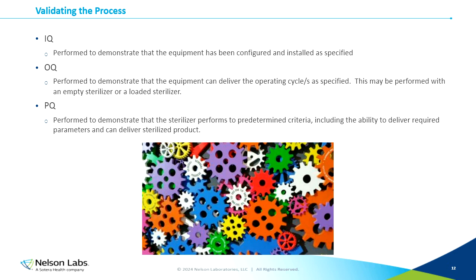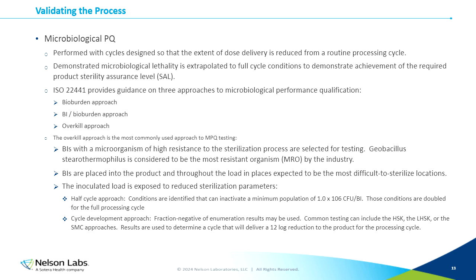Performance qualification is conducted to demonstrate that the sterilizer performs to predetermined criteria, which includes the ability to deliver required parameters and to ensure that the process can deliver sterilized product. Now, when we're talking about the performance qualification, one of the first things we'll look at is microbiological performance qualification. That is performed with cycles designed so that the extent of dose delivery is reduced from a routine processing cycle. For those of you with a lot of experience with sterilization, I'm sure you've heard of half cycles. That might be how we achieve dose delivery that is reduced from a routine processing cycle.